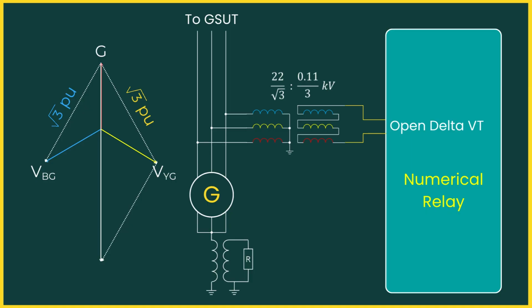Here's why: during a terminal fault, the open delta PT voltage can rise to 3 times the phase voltage, that is, 3 pu. The relay input rating is typically 100 to 120 volts. If a VT ratio like 22 kV/√3 to 110/√3 were used, the open delta voltage would reach nearly 190 volts, exceeding the relay's safe input and risking damage. Using 22 kV/√3 to 110/3 ensures that even under a terminal fault, the maximum voltage at the relay is limited to around 110 volts, keeping it within safe measurement range. For faults 5% away from the neutral, the voltage at the relay drops to about 5.5 volts, ensuring reliable detection. Hence, the relay is configured with a pickup around 5 volts, providing effective protection for 95% of the winding.